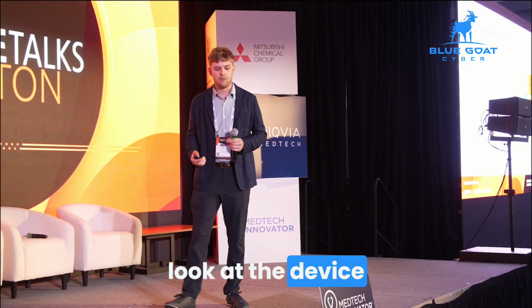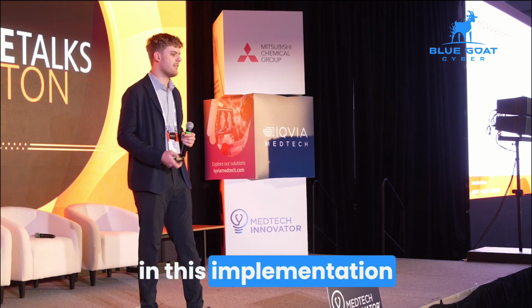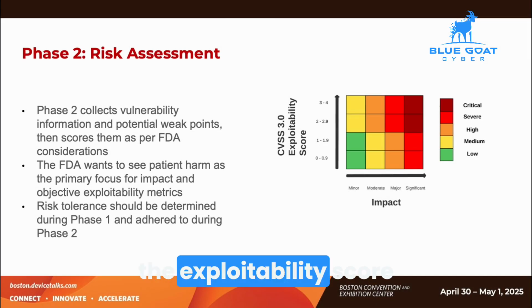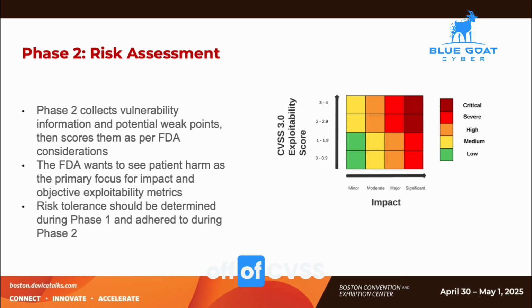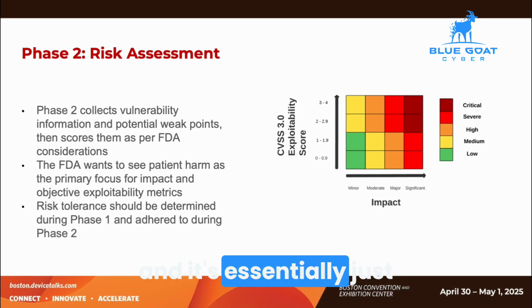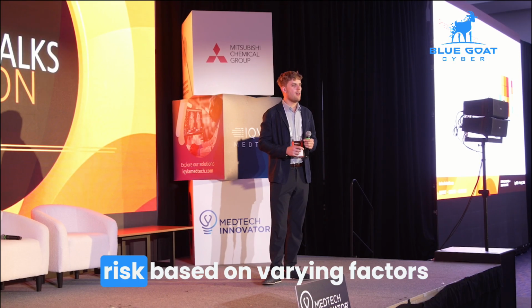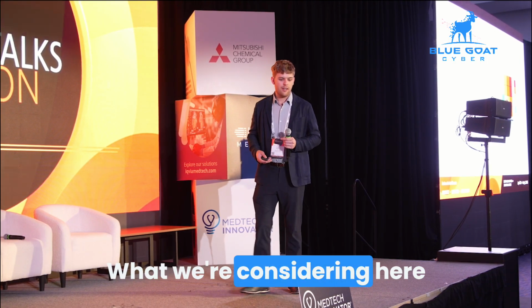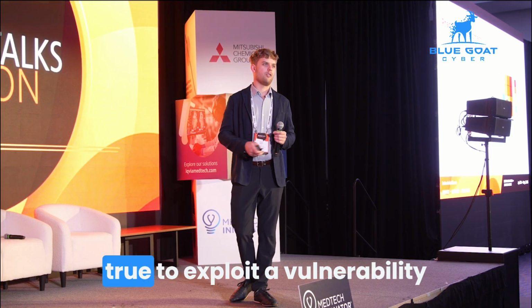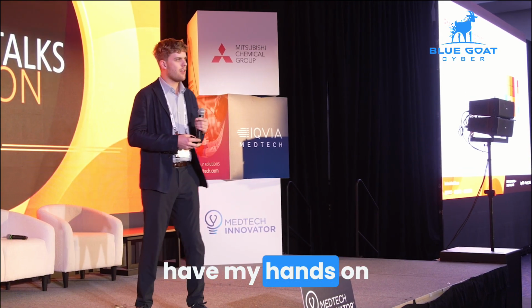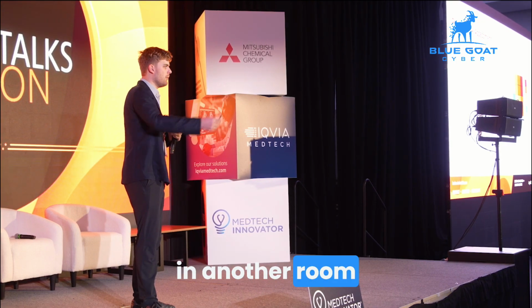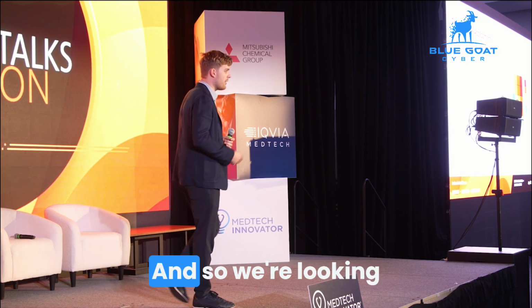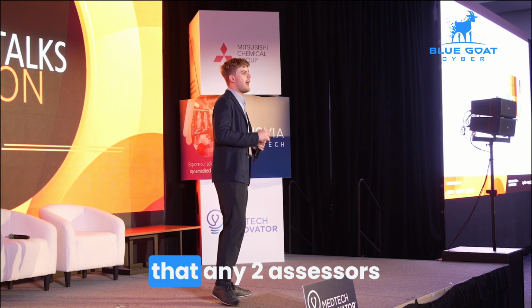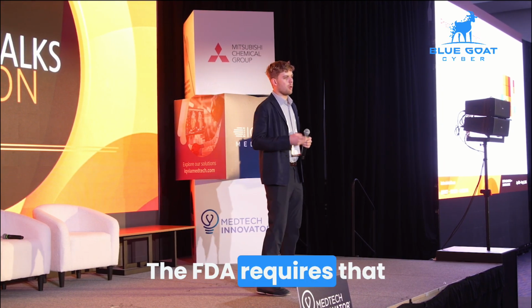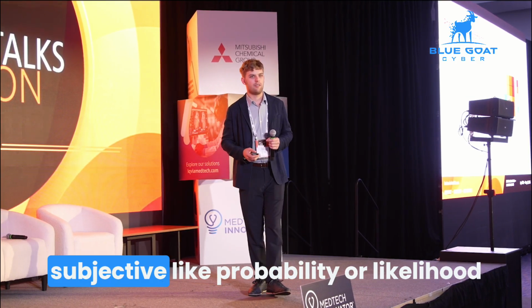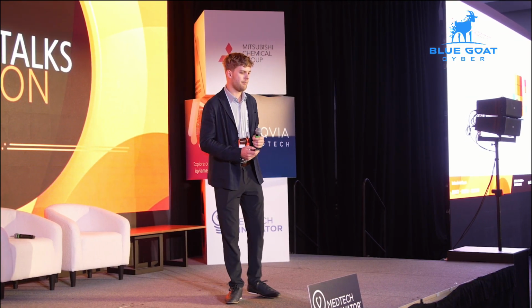So we have to look at the device. We have to understand what is the risk in this implementation. When we're looking at the exploitability score, this is based off of CVSS, which is a system, essentially just a formula for scoring risk based on varying factors. What we're considering here are the situations that must be true to exploit a vulnerability. Do I have to have my hands on the device, or can it be in another room? Do I need to have a password to do this? And so we're looking at objective metrics so that any two assessors come to the same conclusion. The FDA requires that these are objective. You can't use something subjective like probability or likelihood. They don't want to see that.